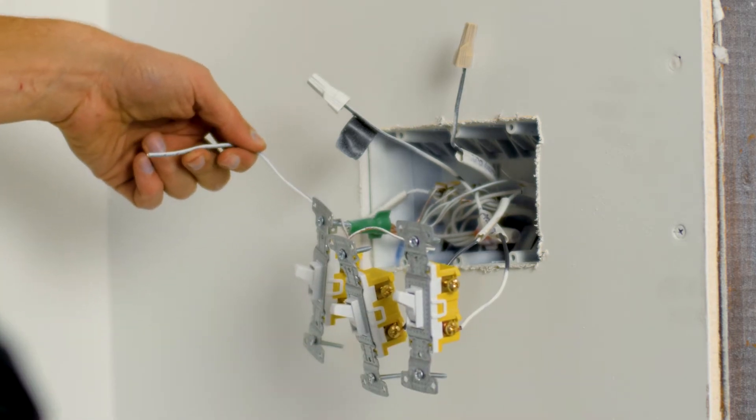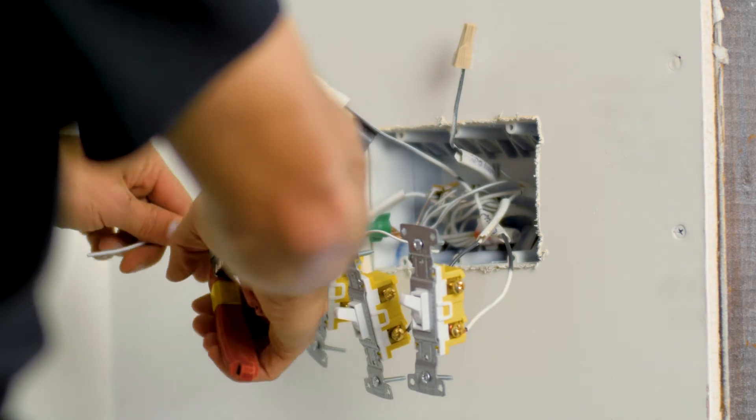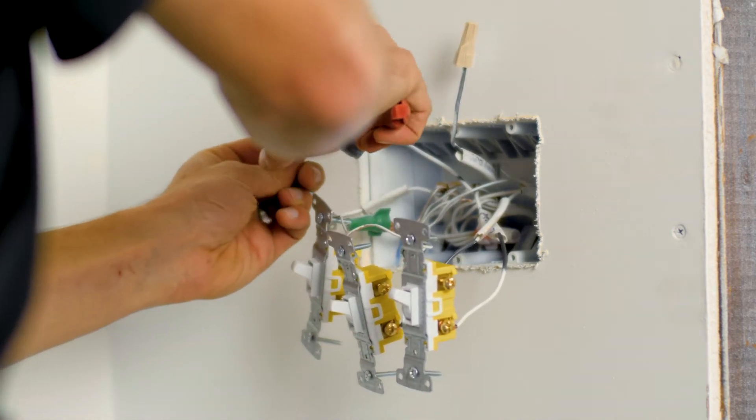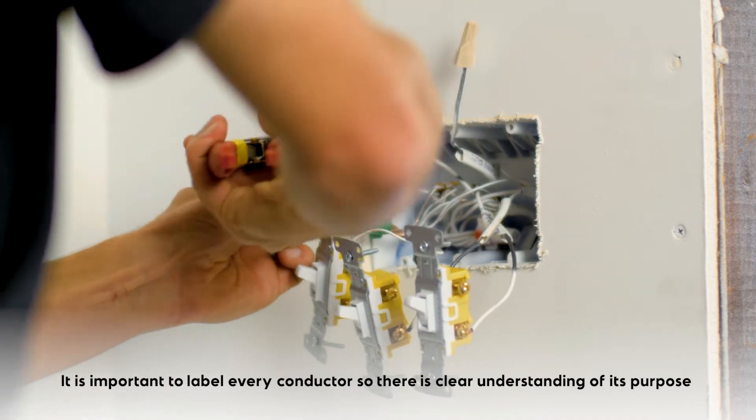This requires a hot feed. That's my hot pass out of the box. This is my final switch leg here, and this is my hot into the box designated by the flag. It's important to label every conductor every time to make its purpose and intention clear for a clean finish.